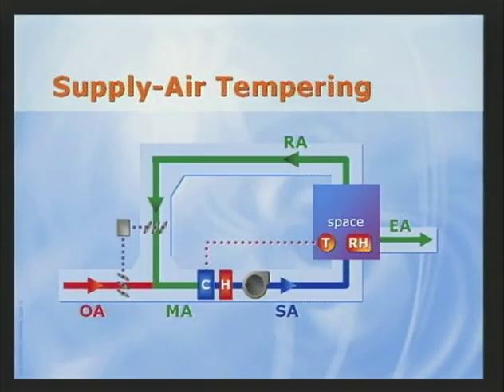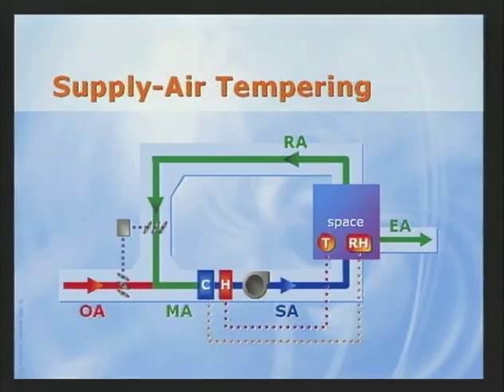The second dehumidification enhancement we'll discuss for a chilled water terminal system is supply air tempering, or reheat. This configuration includes a source of heat downstream of the cooling coil and a humidity sensor located in the space. In the normal cooling mode, the capacity of the cooling coil is modulated to maintain space temperature at set point. However, if the humidity sensor indicates that space humidity is higher than the desired limit, the system switches to dehumidification mode. In this mode, the capacity of the cooling coil is increased, dehumidifying the air enough to maintain space humidity, and the downstream heating coil raises supply air temperature just enough to avoid overcooling the space. Now, this enhancement provides a means of directly controlling space humidity.